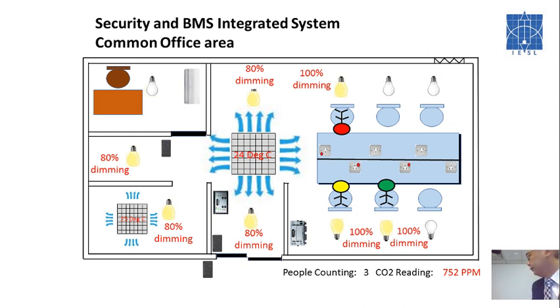People counting is now 3, and CO2 is 752, which is not very healthy for the environment to work in. So we switch on the fresh air damper to 18% to reduce the CO2. As the CO2 reduces to 515, the fresh air damper decreases to 10%.